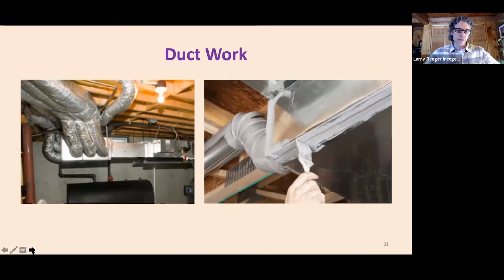You have to be really careful how the ductwork is run for it to be efficient. When I see flexible ductwork, I cringe a little, because it's the cheap way to install it, every strap restricts the airflow. You want all your ductwork open and free-flowing, not kinked, so the system isn't working too hard. On the right, that's mastic, the method you use when you have a lot of galvanized steel ductwork.